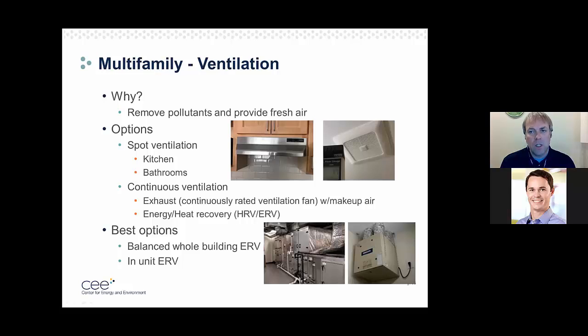With the ERVs and HRVs in units, it's a little lower cost than the central ERV/HRV, but it's going to be increased maintenance, because there are more units throughout the building. So you have one per apartment to check, which again, if you're already having someone in there change the furnace filter every month or two, it's just one more quick check to do, but it can be done - it's just a little more time involved.